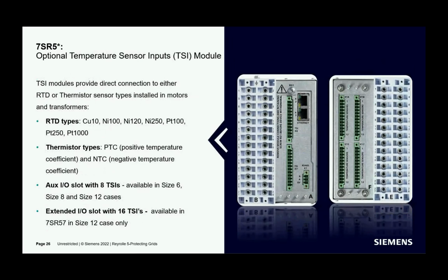So let's talk about temperature sensor inputs. Again, for complete protection application, especially for transformers and motors, 7SR5 devices have the option for temperature sensor inputs for connecting to temperature sensors in the field. We call it TSI as an abbreviation. The TSI module supports a wide range of RTD and thermistor sensor types available on the market. And the TSI module is available for all 7SR5 devices optionally with 8 temperature sensor inputs. But exclusively for 7SR57, the motor protection relay, the TSI module is available with 16 temperature sensor inputs. And this 16 input type module is available only in size 12.